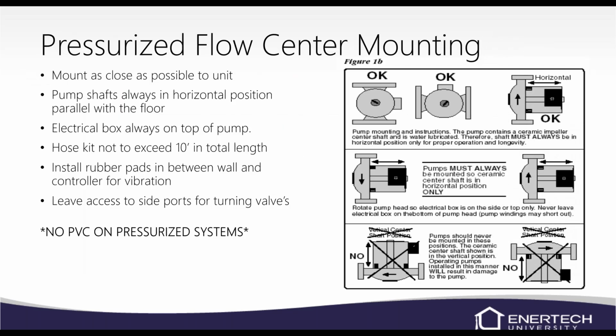Pressurized flow center mounting. Mount as close to the unit as possible. When we do pressure drop on our units, if you need pressure drop for, let's say, a WTO 60, so you can size your pump, we factor in the heat exchanger, the piping that's in the unit, and also the 5 foot of hose kit, or the 10 foot, 5 foot each way. We calculate that into our pressure drop. So if you have a longer distance between your unit and the flow center, then you may want to put that into your calculation when you're sizing your pump. But we do put in there for 5 foot each way.